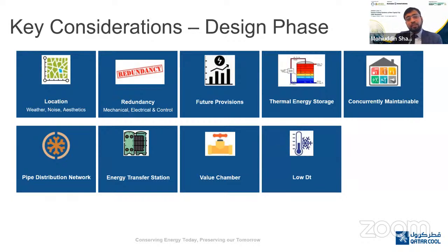Low delta T, special attention should be given, because inherently all the DCPs at some point of time would encounter the low delta T syndrome, which is that customers would not be able to return the water at the design temperature. So if the return water temperature is lower than the design, that would impact your pumping volumes. You will have to pump more water, spend more energy on pumping, and add additional chillers to meet the temperatures. So that would significantly scale up the operational cost.